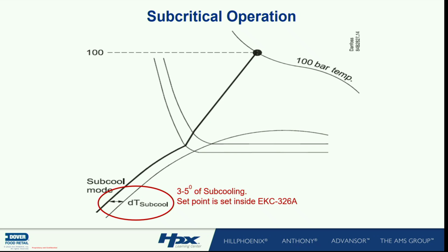If I draw this line 5 degrees off the liquid saturation line, then I'm 5 degrees - if I'm right here, I'm 5 degrees subcool. So what's he doing, why is he moving like that? He's regulating coming out of the gas cooler based on COP and the temperature of the sensor coming out. He wants to be here to make this the most efficient system possible.